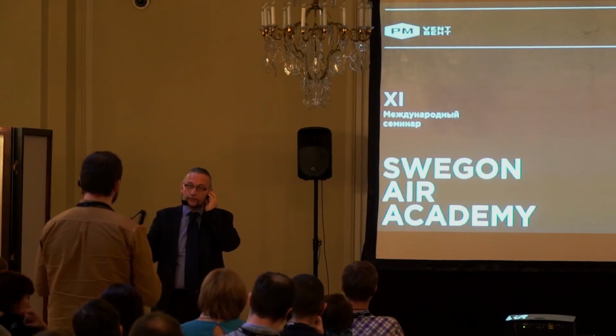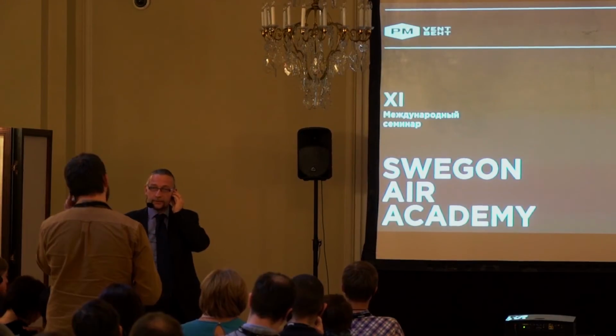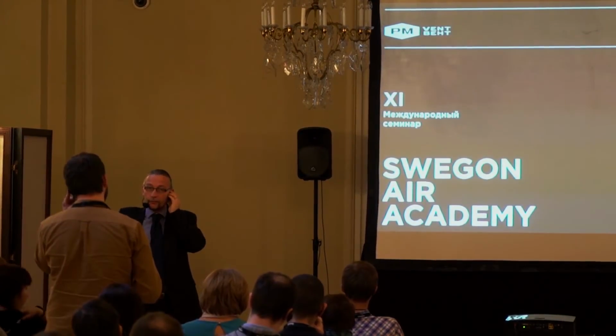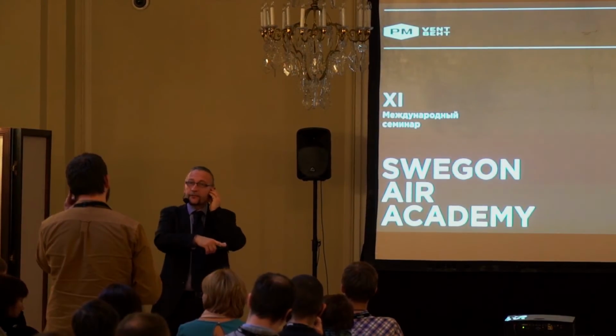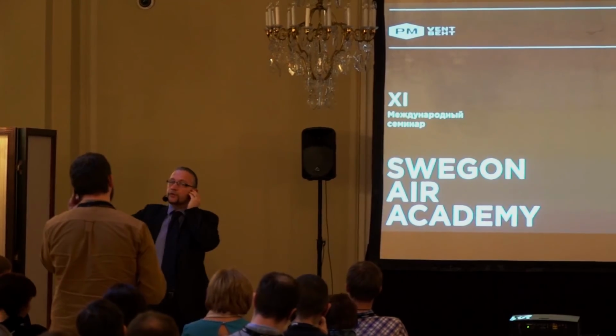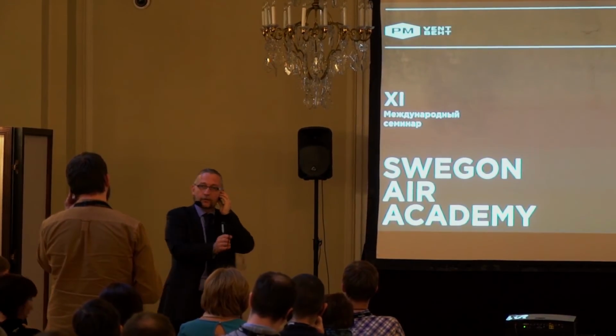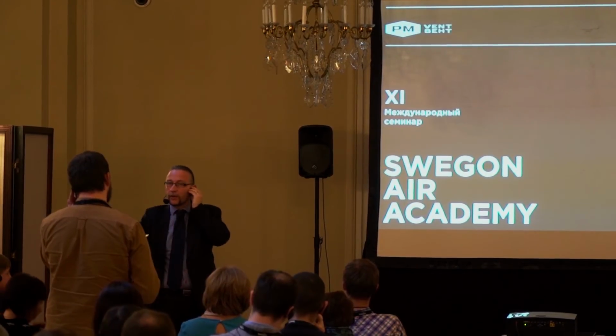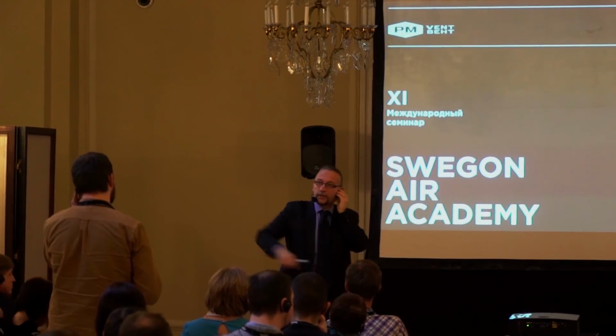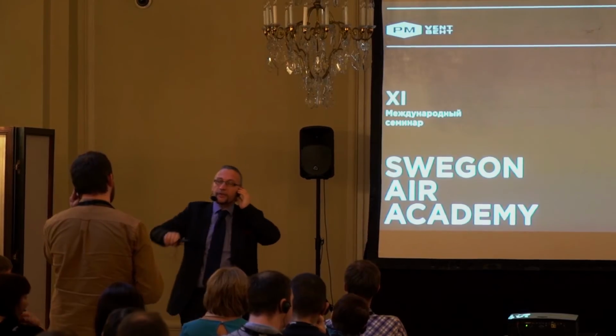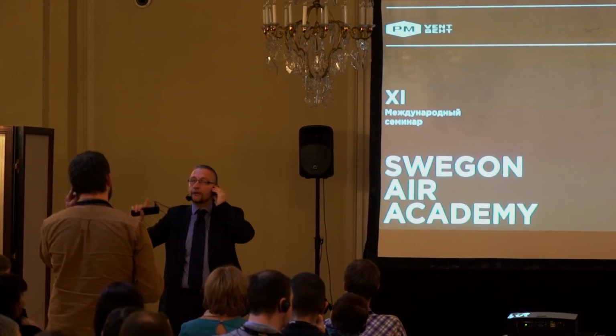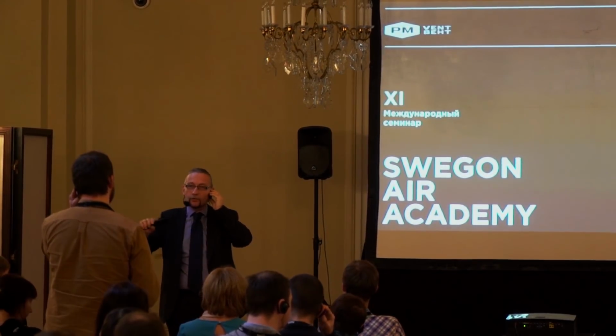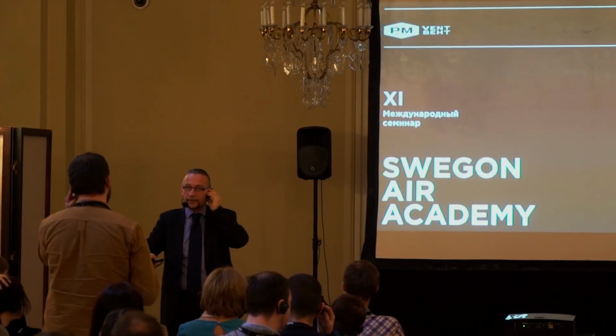It's two parts. The whole building has to be in balance, of course. So supply and extract have to be in balance. But the extract in this room will follow the supply. It's a slave control. The damper knows how much air goes out. So if now 400 cubic meters are going in, over there 400 cubic meters are going out. Now this one goes up to 500. This one will go up to 500. This room will be in balance. And the rest of the house will be in balance. So you don't get overpressure, you don't get underpressure in here.